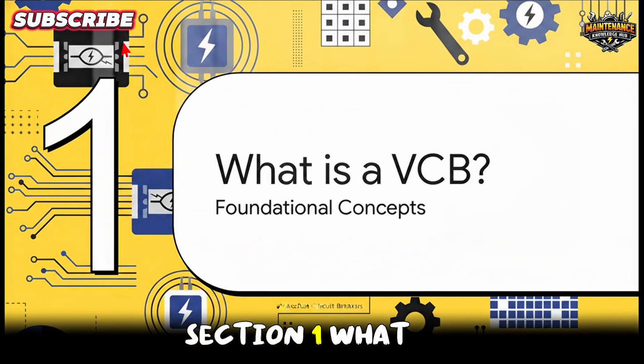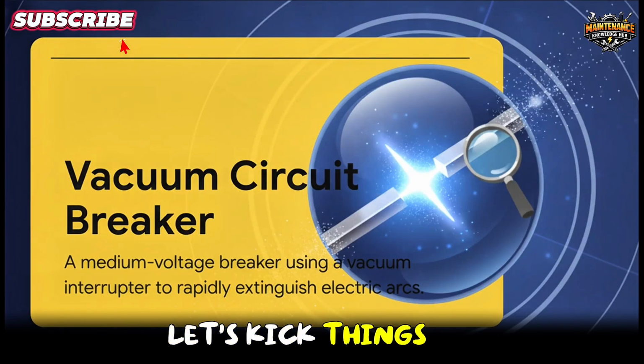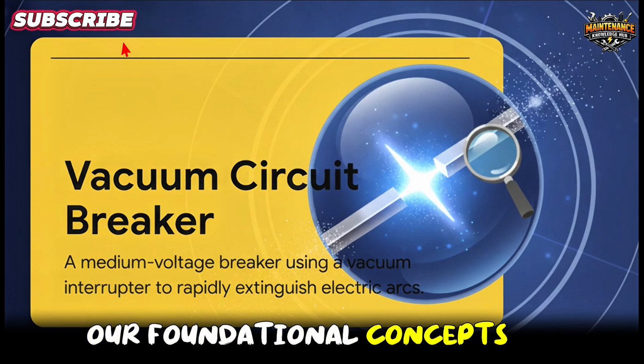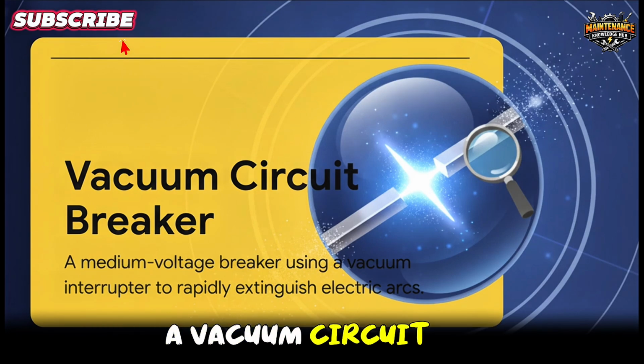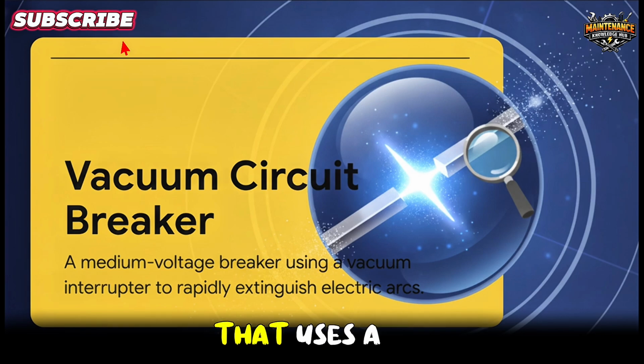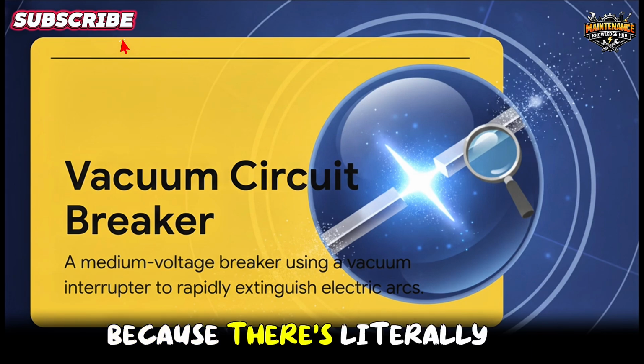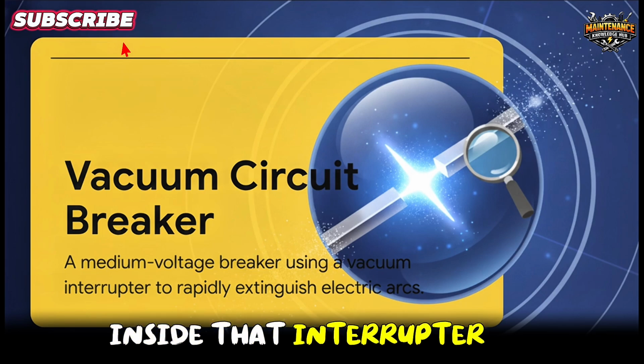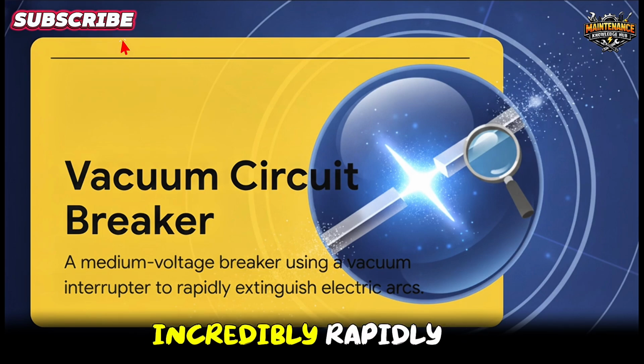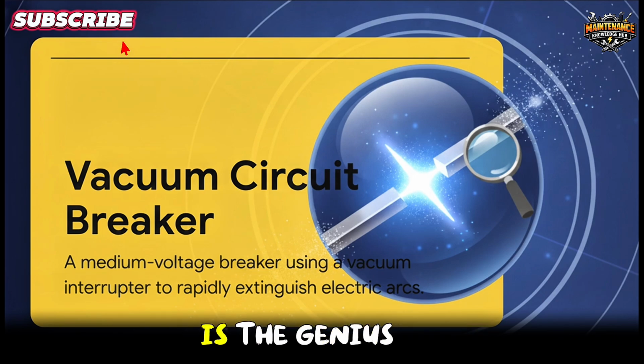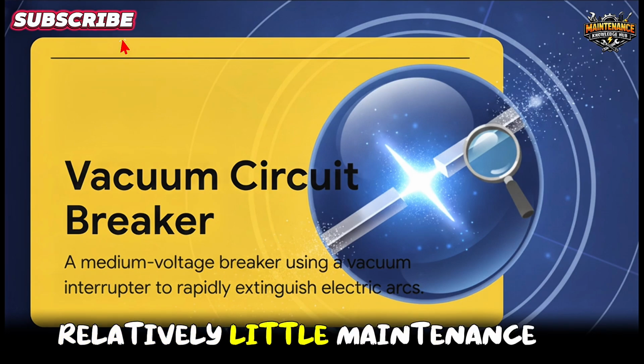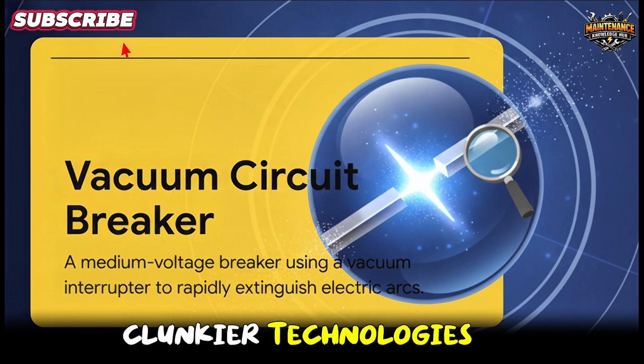All right, section 1. What is a VCB? Let's kick things off by establishing our foundational concepts. So, by definition, a vacuum circuit breaker is a medium-voltage circuit breaker that uses a vacuum interrupter to extinguish the electric arc formed when interrupting current. The real magic here, the whole secret sauce, is the vacuum itself. Because there's literally no air or gas inside that interrupter, the arc extinguishes incredibly rapidly. That rapid quenching is the genius behind its high reliability. It's exactly why this thing requires relatively little maintenance compared to older, clunkier technologies.